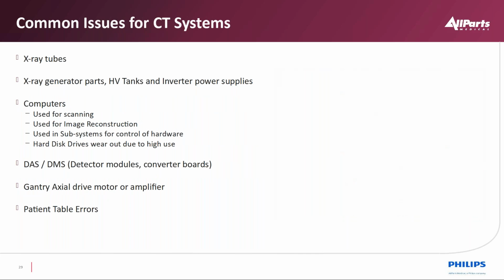So X-ray tubes are a common issue that we have. Sorry, X-ray tubes are the highest expense that we have. Then the next highest expense would be X-ray generator parts that support it, high voltage tanks, and then eventually computers, and then detector modules. We see detector modules that crystal will age out. Crystals and X-rays do not like each other that often, and so we'll see a degradation of the crystals within that module.